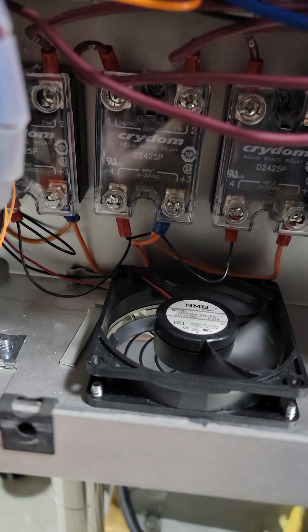We've got contactors, relays, terminal blocks. There's our 3 SSRs, one for each heating element. Remember the old 3870, like most Tuttnauers, has a single SSR for the heating elements, and then you've got your dry pump and your air pump.